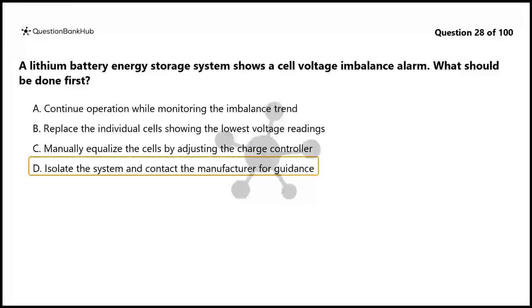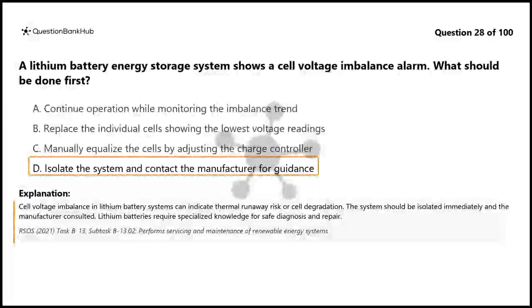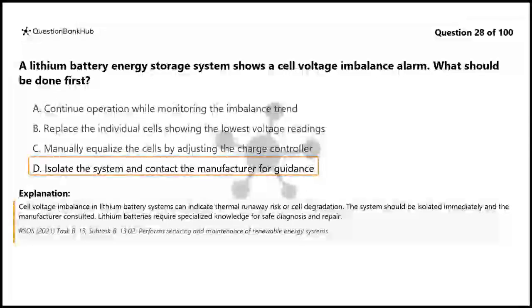The correct answer is D. Isolate the system and contact the manufacturer for guidance. Cell voltage imbalance in lithium battery systems can indicate thermal runaway risk or cell degradation. The system should be isolated immediately and the manufacturer consulted. Lithium batteries require specialized knowledge for safe diagnosis and repair.